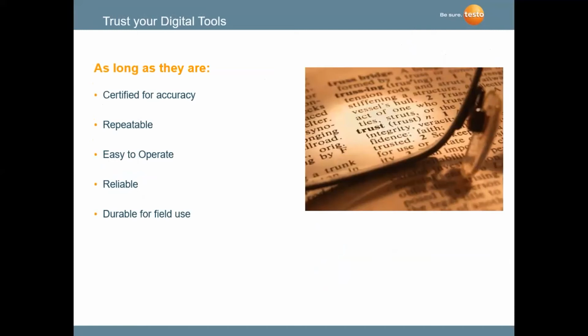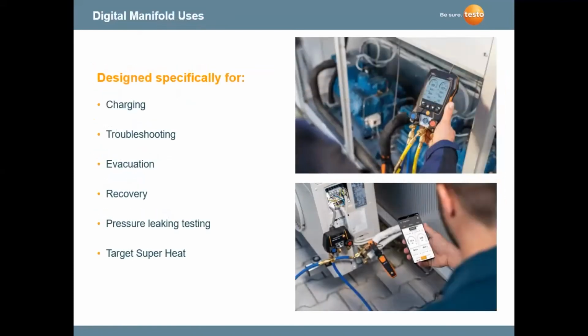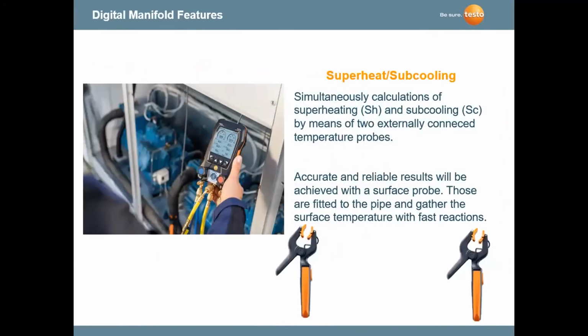Again, these are extremely accurate instruments. Again, ISO certified. They're calibrated. They're very durable. There's a lot of ways of using these digital gauges: charging, troubleshooting, targeted superheat. We went through a few of these already. Superheat, subcooling, where you're using the instrument and you're transferring the temperatures. The temperature pipe clamp probes are now wireless probes that communicate directly into the instrument.